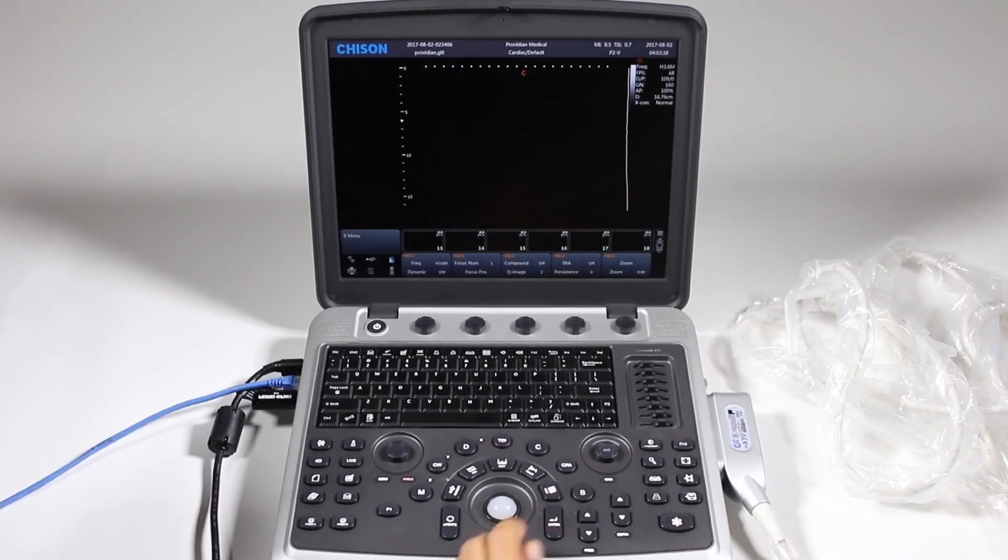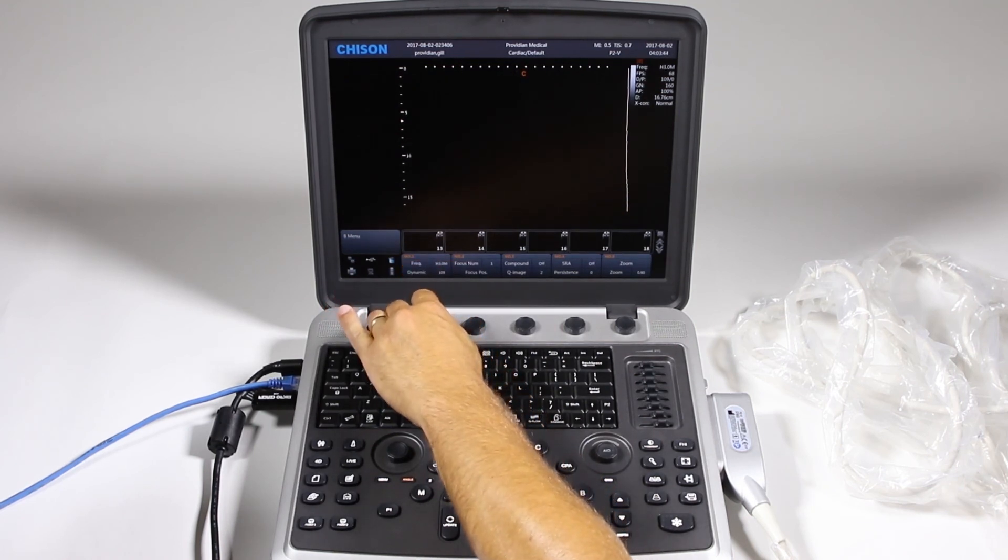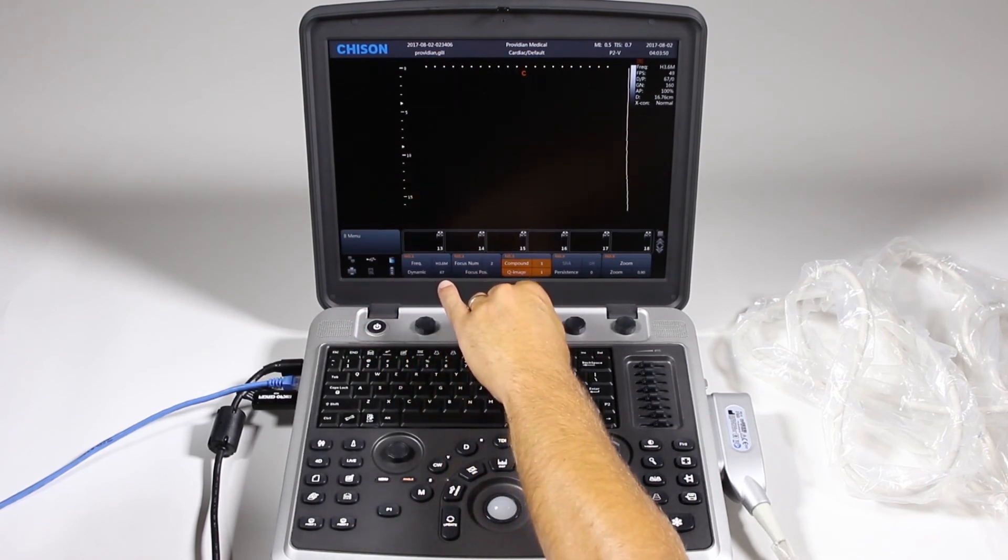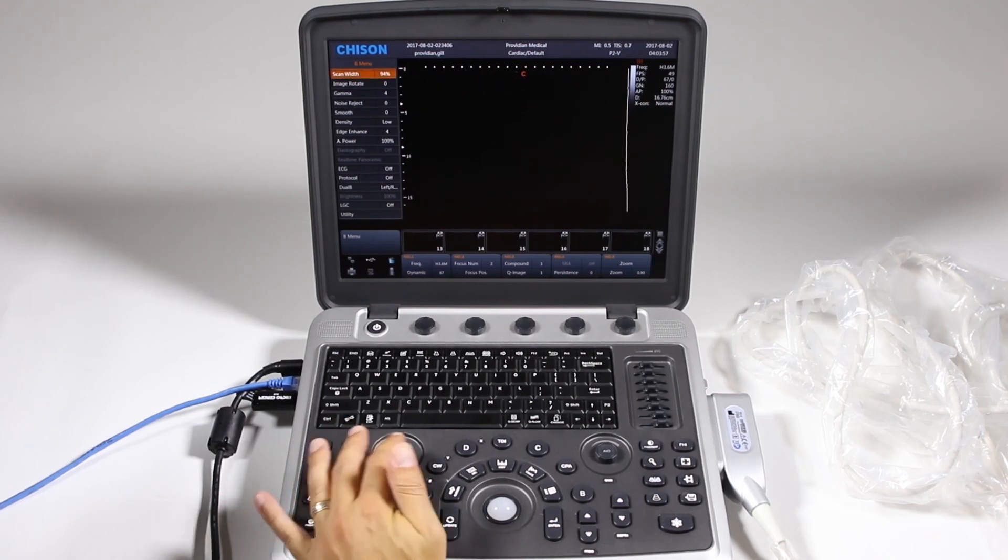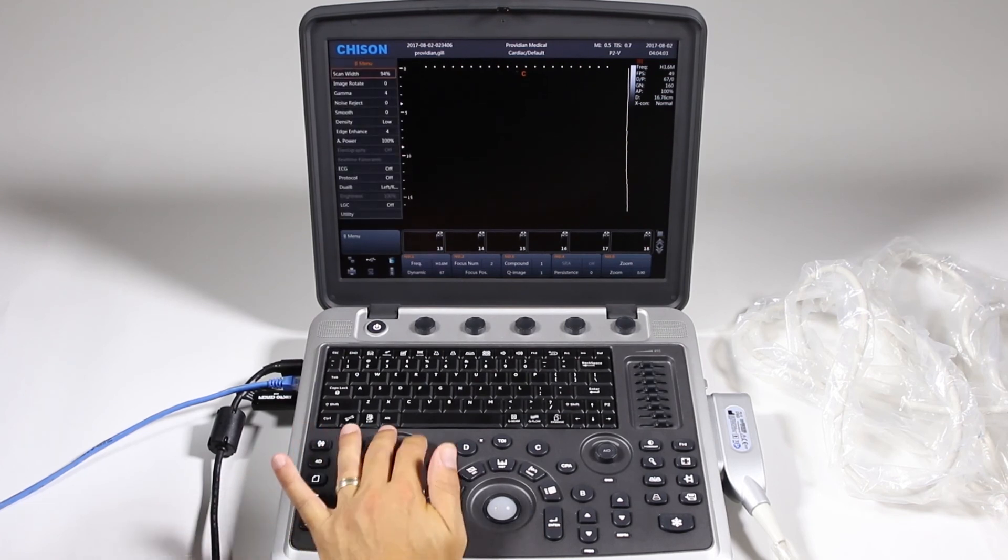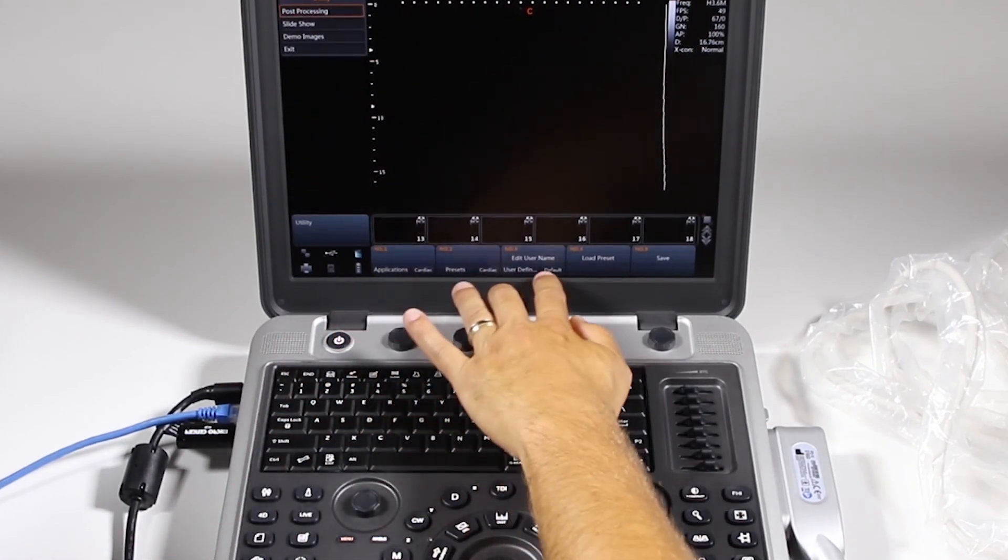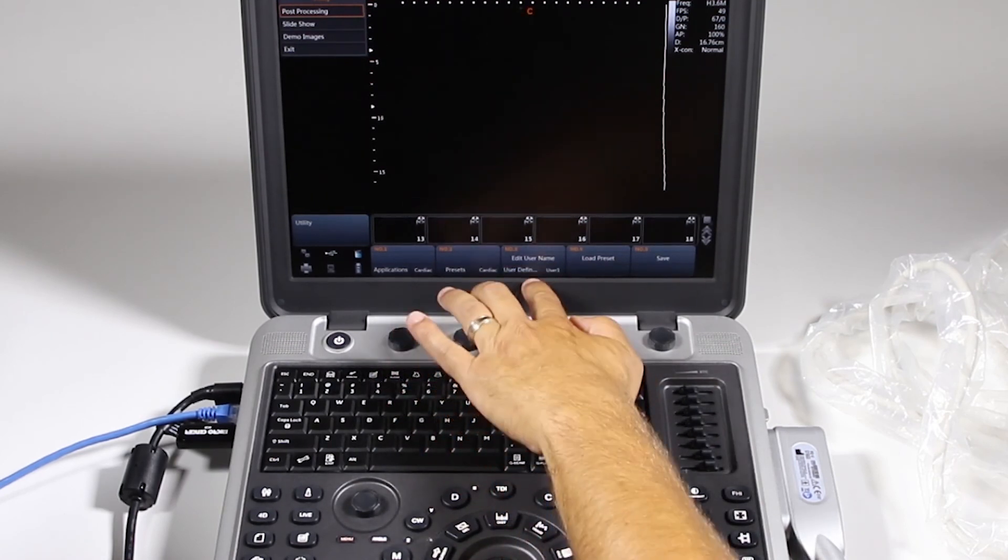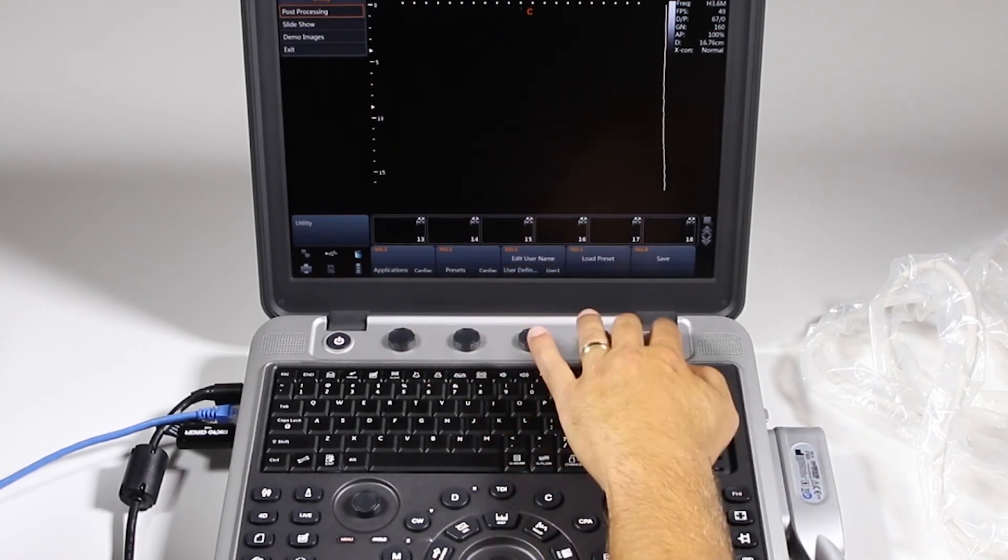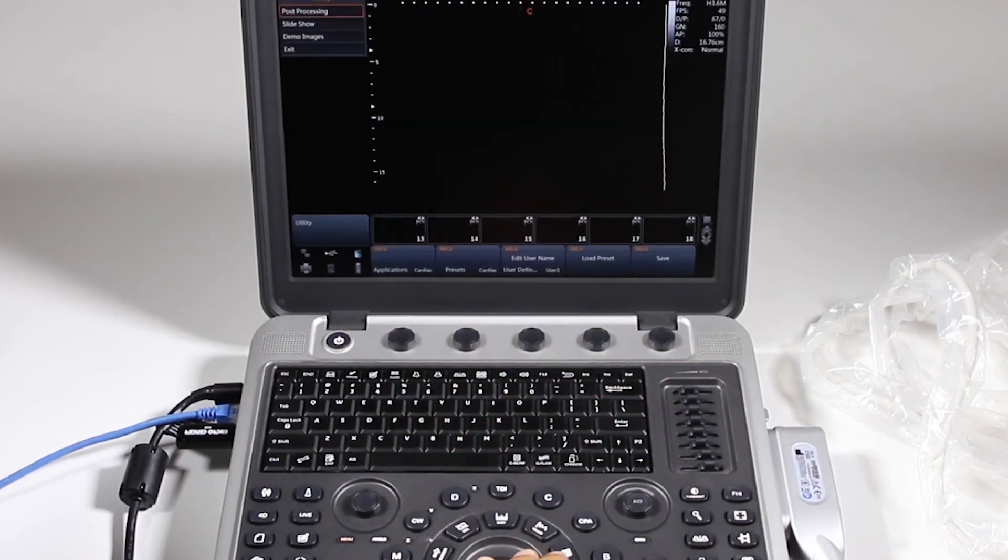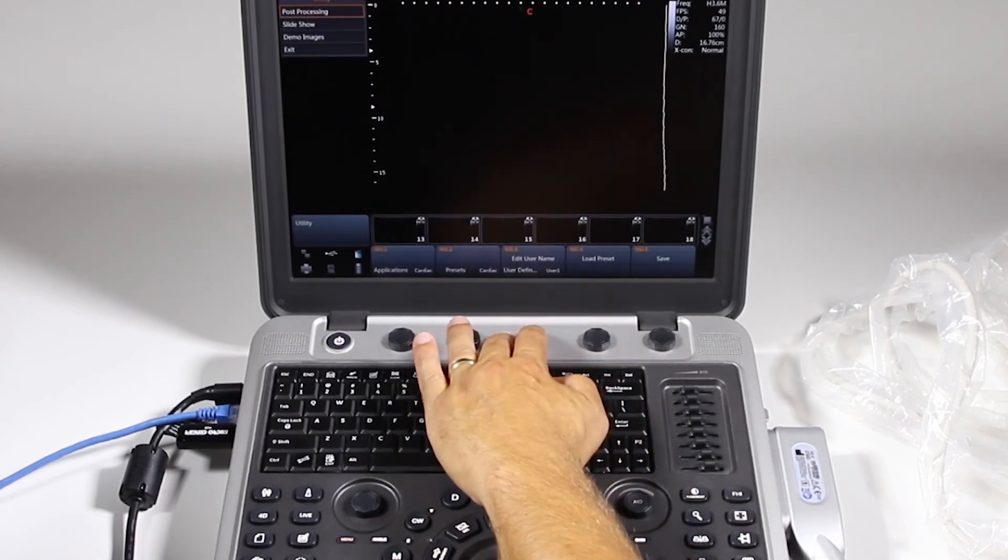Now, if we want to save a custom preset, let's say we preferred our own settings and we made settings that we prefer with a higher harmonic frequency, change our dynamic range, focal position, focal numbers, compound imaging, etc. And say we really like that image, and this includes the parameters up here when you click that menu key down. To save your own custom preset, press the menu button down. Go to utility. Then, down here, say applications, presets, edit username, etc. I want to create my own user defined, so I'm going to change this to user 1. Down here, and I can choose 1 through 5. I'm going to go ahead and check user 1. I'm going to click save. And then I want to save this current preset to cardiac. That is correct. And I clicked OK. So now I've got one under user 1.